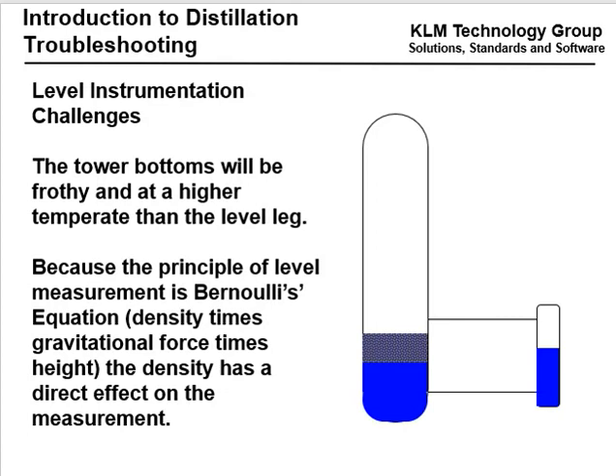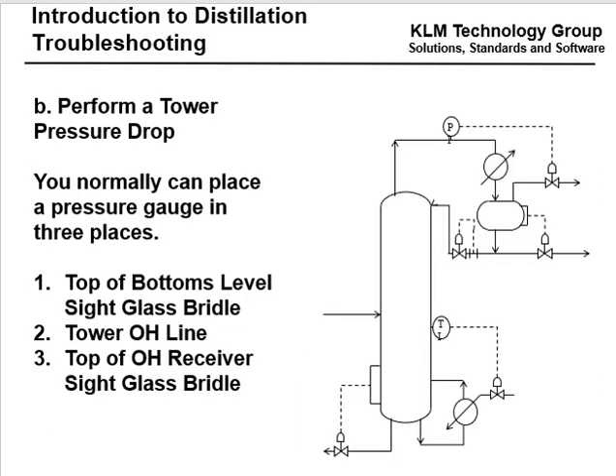Level instrument challenges: the tower bottoms level will be frothy at a higher temperature than the level transmitter. Because of the principle of level measurement — density times gravitational force times height — the density has a direct effect on the measurement. In hot service, the level in the tower is typically always higher than the level in the sight glass. So verify the levels.